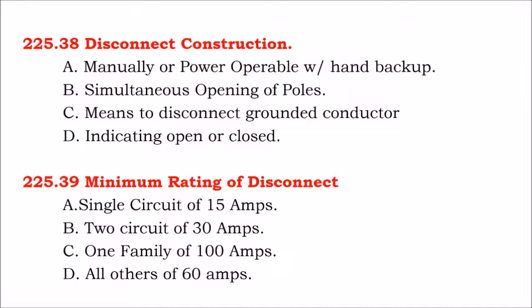And those motorized breakers right now cost about 120 to 130 bucks. But the rules on those motorized breakers, if they're going to qualify as the disconnect, they also have to be hand operable. So sometimes the little tab will stick through the motor and you can wiggle the tab back and forth by hand, but the motor will still also separately operate the breaker. Otherwise, they need to be separate. The disconnects need to operate both poles, both positive and negative poles. They can have the means to disconnect the neutral, the grounded conductor. They need to indicate if they're open or closed.